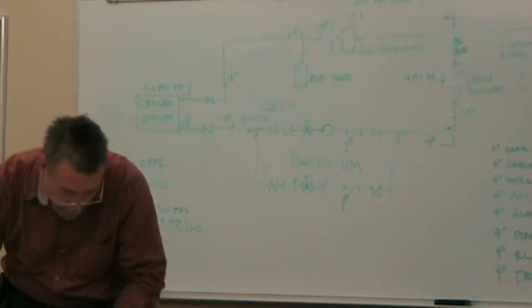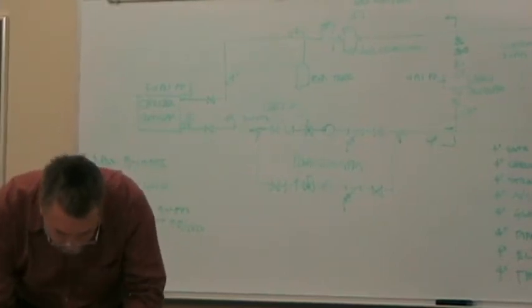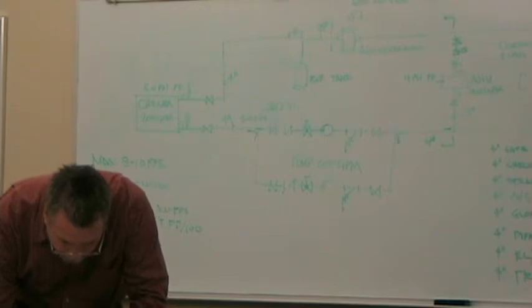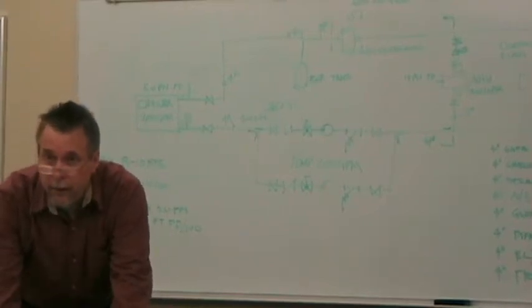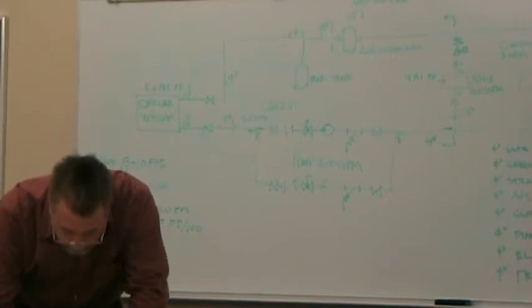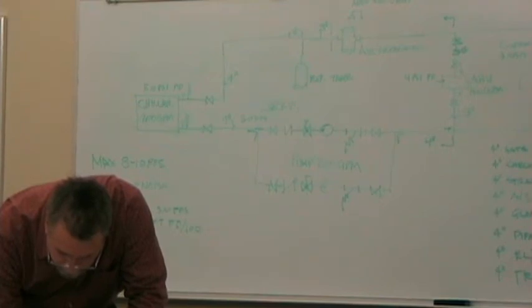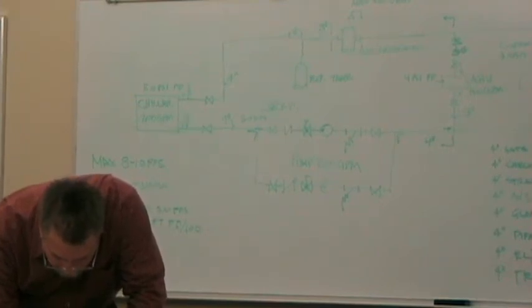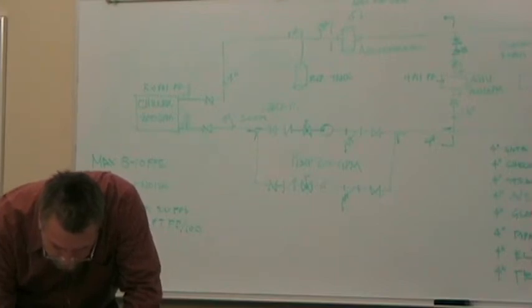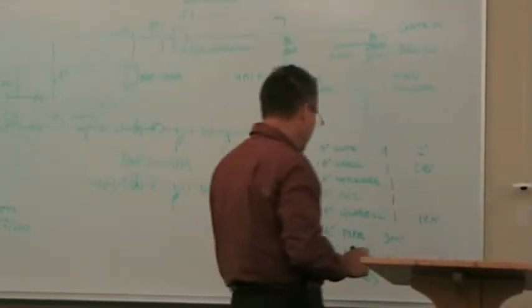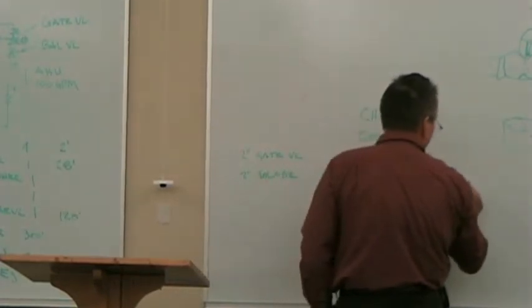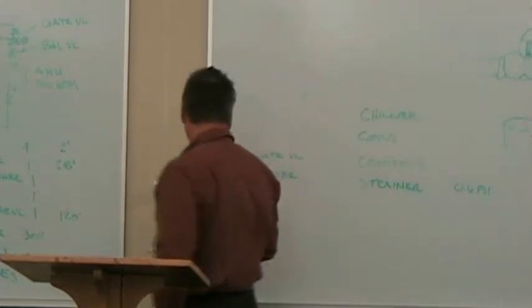Strainer. Pipe pattern strainers, 2 4-inch. I'm just going to use a line size strainer, even though I don't have to. If you use a bigger one, it costs money. If you use a smaller one, it costs energy. So a 4-inch line size strainer at 200 gallons a minute has an actual pressure drop of about 0.6 psi. So I'm going to move that over to here. Strainer, 0.6 psi. That's ideal condition, so that's a clean strainer.